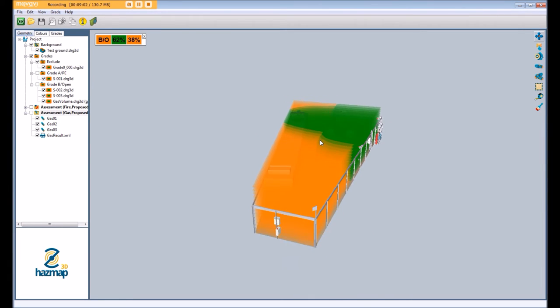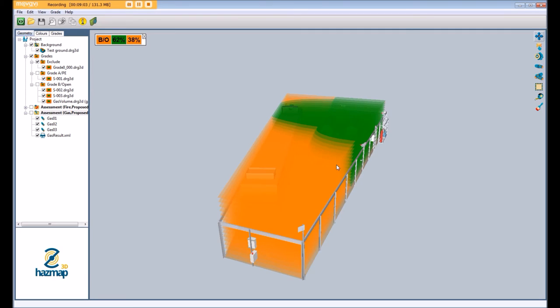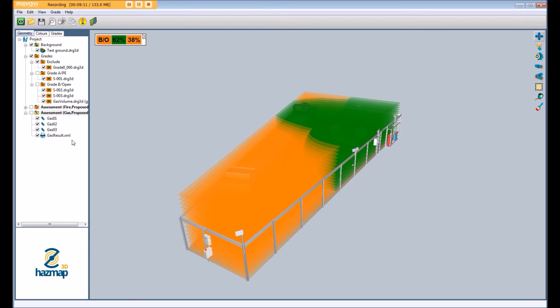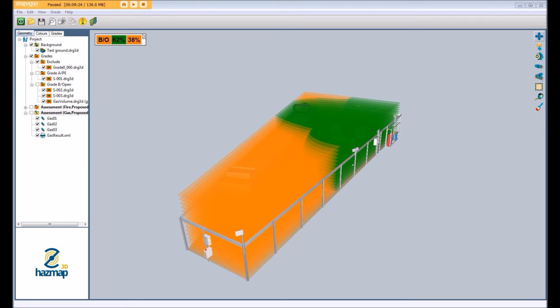It's important to note within the dilute and dense cloud model we incorporate in the beam attenuation model which essentially calculates the concentration of the gas, the given gas cloud across the beam and calculates out whether that will actually provide an alarm or an executive action based on the specific open path and the specific set point of that environment and the facility.